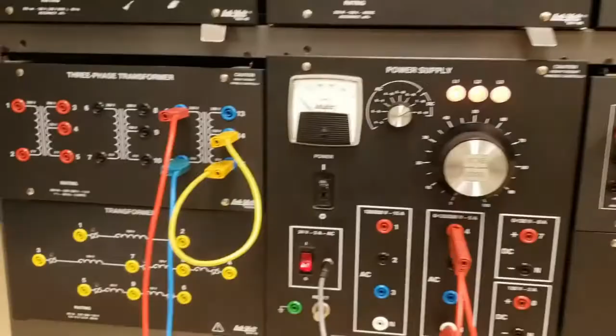So actually, I'm not going to go directly to rated voltage. I'm going to do 30%, 60%, and then 100% rated voltage. And each one will have its own IOC. And the reason why I'm having us do the 30%, 60%, and 100% rather than just rated voltage right away is I said that the open circuit test has its limitations, that the parameters you get are just for that voltage level. You're going to see that now, or at least you should.